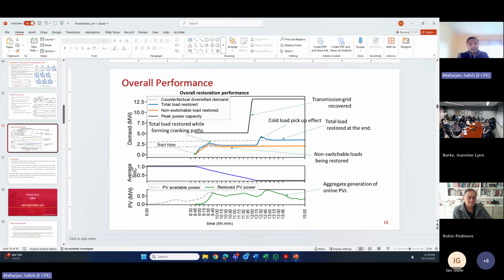Yeah, right. So in this study, we know when the transmission grid will come online. So based upon that information, the SOC of the battery has to be utilized in such a way, right, that it can sustain the critical loads until the transmission grid comes back. So basically here non-critical loads are sacrificed. I mean, they are not picked up if the problem finds out that the outage duration is long and we need to pick up only the critical loads and sustain them until that point.